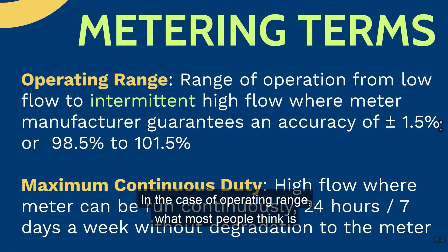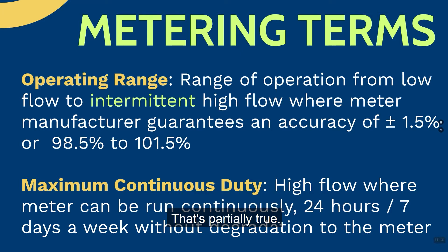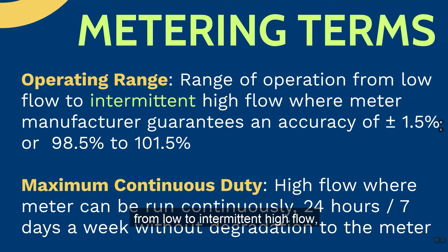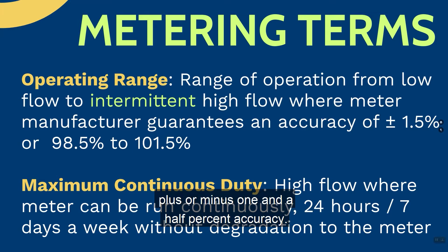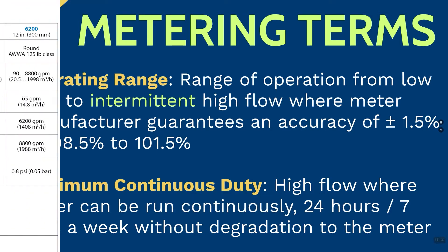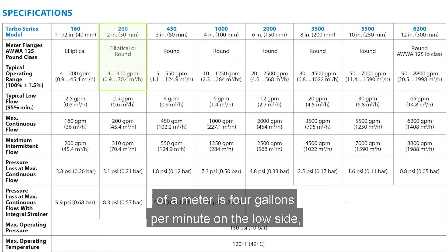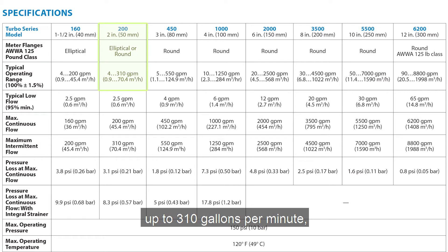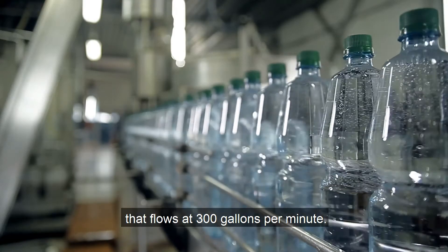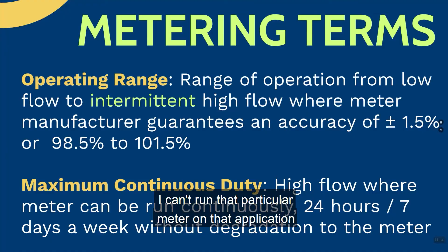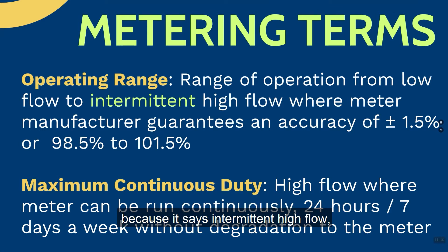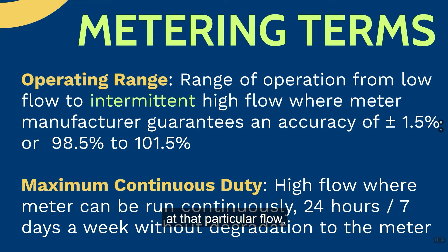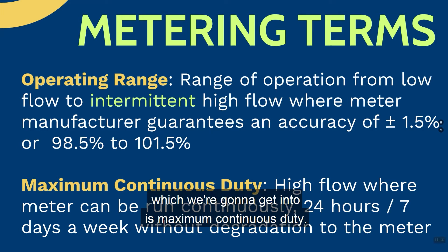In the case of operating range, most people think this is where the meter should operate from low to high. That's partially true. What the manufacturer normally states is this is the range of operation from low to intermittent high flow where the meter is guaranteed plus or minus one and a half percent accuracy. For example, if a meter's operating range is four gallons per minute up to 310 gallons per minute, and a customer application flows at 300 gallons per minute continuously, I can't run that meter on that application — because the 310 GPM figure refers to intermittent high flow. That leads to the next term: maximum continuous duty.